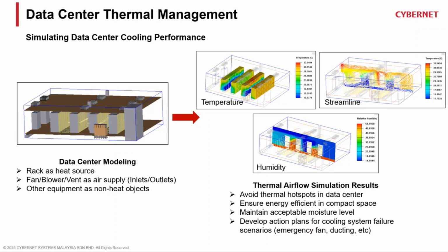So with the help of CFD, you can actually simulate those kinds of scenarios. Let's say a certain fan is not moving, or this or that aircon is not operating, what will my data center look like? Will it accumulate a lot of heat? Then what is the plan? Whether I need to install some emergency ducting or escape vent, or more aircon just on standby. So you can simulate those different configurations or fail-safe plans to model the scenario itself.